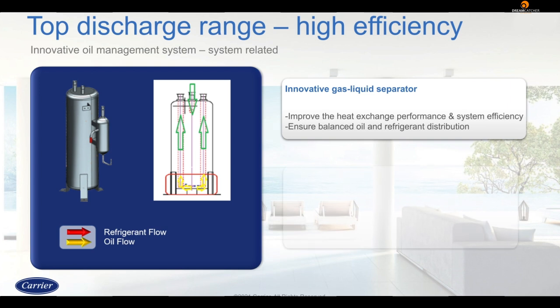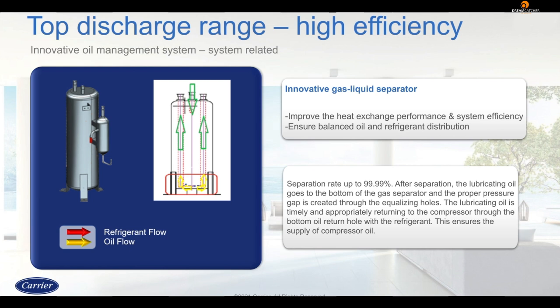The system ensures a separation rate of 99.99%, where the lubricant oil goes to the bottom of the separator and a pressure gap is created through the equalizing holes, and the bottom oil return hole sends the oil back to the compressor.